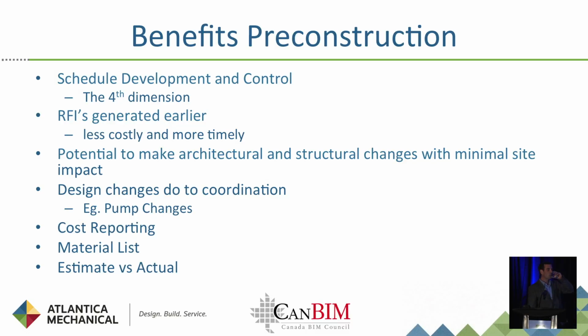Design changes due to coordination is one a lot of people don't talk about, but we've seen it in a few jobs. Domestic water systems, for example, don't often get fully coordinated in the design intent process, and they size a pump according to X number of fittings, certain linear feet of pipe, all of those things. If you don't do proper spatial coordination, which is a huge element of BIM, and you start installing that pipe and put in 32 extra elbows, all of a sudden your pump is now operating at a different point on its pump curve, hopefully still within that curve, because if you exceed the pump curve, guess what? You're taking that pump out, that's probably already been bought, most likely installed. You're taking it out, putting it back in. Now you've got a different pump. You have one pump that's no good. You've got all the costs associated with that from a contracting perspective. It can be a big deal.